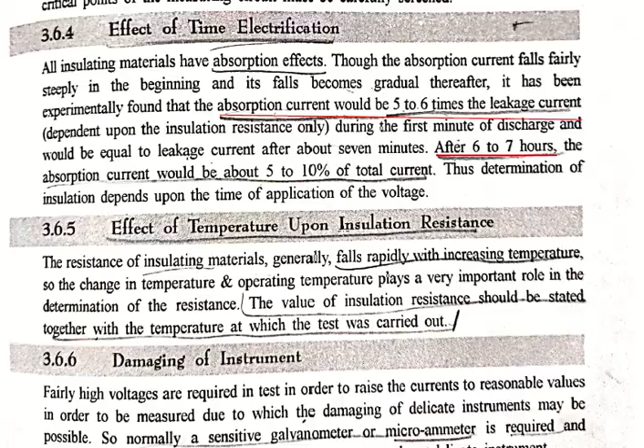Effect of temperature upon insulation. We know that the resistance of insulating materials generally decreases with increasing temperature. So the change in temperature and operating temperatures play a very important role in the determination of the resistance. The value of insulation resistance should be stated together with the temperature at which the test is carried out. We have to mention the temperature of the surrounding also.